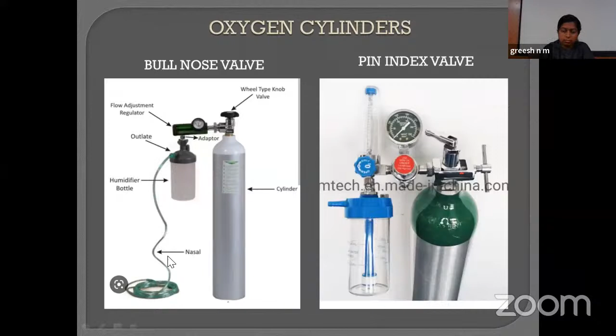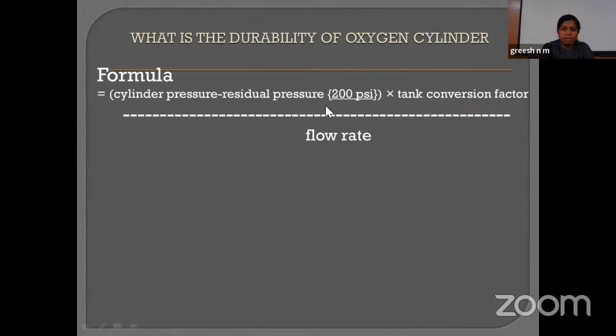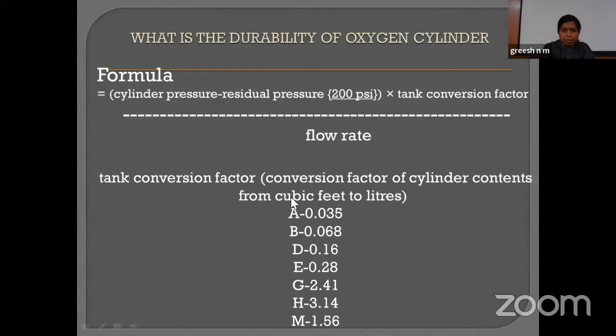Now, what is the durability of the oxygen cylinder? For this, there is a formula: cylinder pressure minus residual pressure, into tank conversion factor, divided by flow rate. What is this residual pressure? Residual pressure is that pressure in the oxygen cylinder below which there is no efficient flow of oxygen to the patient. This is always constant, which is 200 psi. Tank conversion factor is a conversion factor of the cylinder contents from cubic feet to liters, and it is constant for different varieties of cylinders.